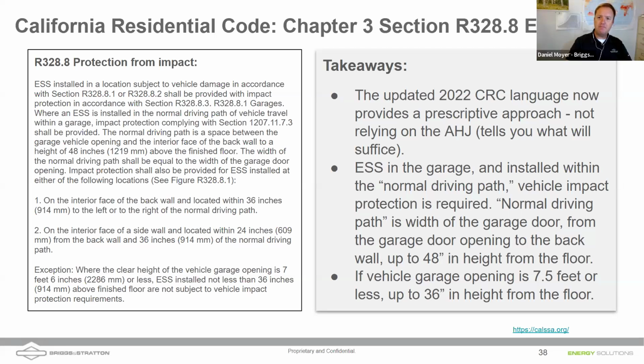If the vehicle garage opening is 7.5 feet or less, and you have the battery 36 inches above the floor, you don't need to put a parking bollard in, even if it's on the back of the garage where somebody could crash into it. Is that a scenario you see can be achieved? And how high is a standard garage door? I think it's 84 inches, so that's 7 feet. I believe they're talking about the width here, but maybe I'm incorrect—so it's not clear from this whether they're speaking about the width.